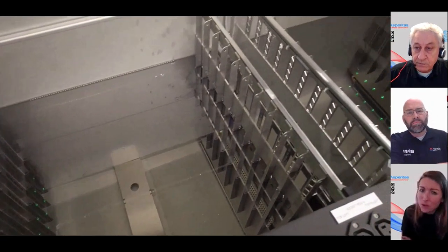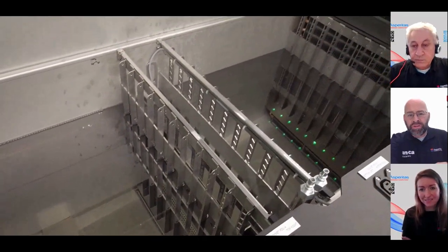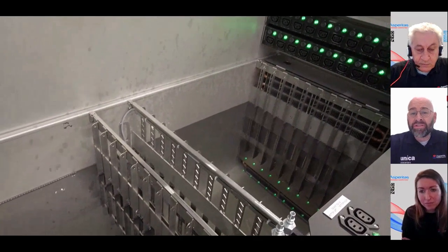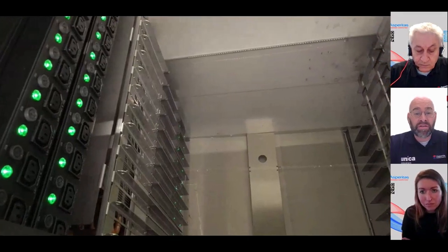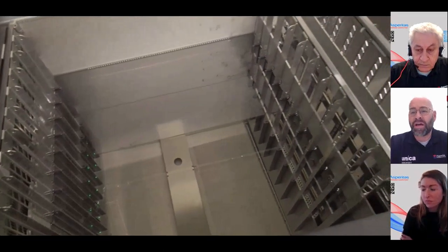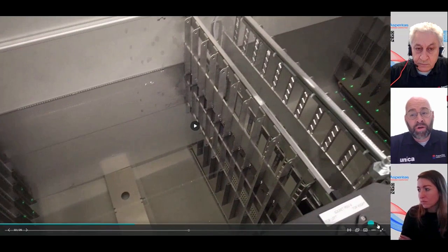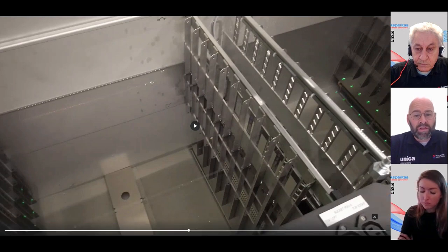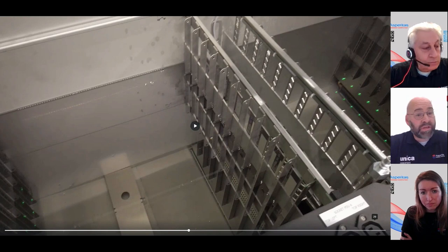Marco, what about from Unica's perspective? Yeah, maybe to add a little bit about the connectivity. We mentioned already that we have standardized the interconnection based on proven and best industry practices. From that point of view, we minimize any risk of leakage outside of the module. Next to that, part of our maintenance check is that we double check all connections and appendages to the system preventively. What we normally see in data centers is that clients also check during visual inspections for any issues with systems. In some bigger installations, and I expect this to be used with emerging cooling technology, surrounding areas will be checked by monitoring systems, leakage detection systems, for example through sensors or sensor cables.